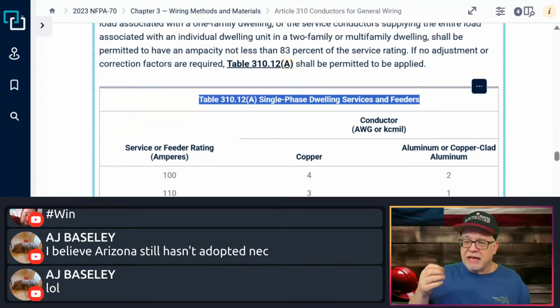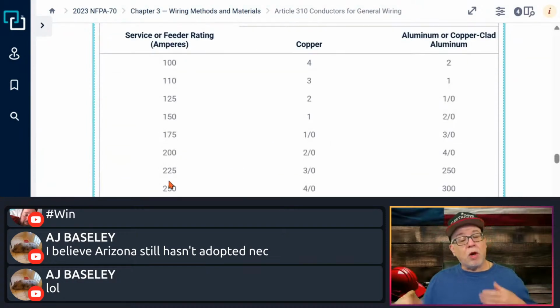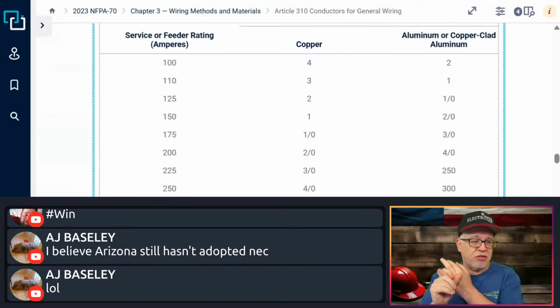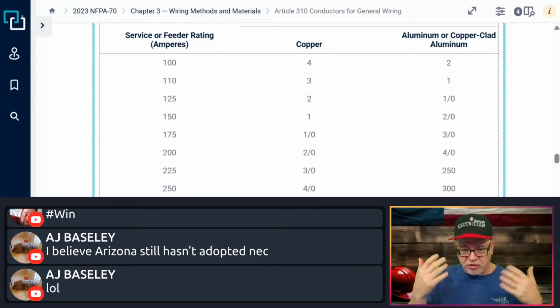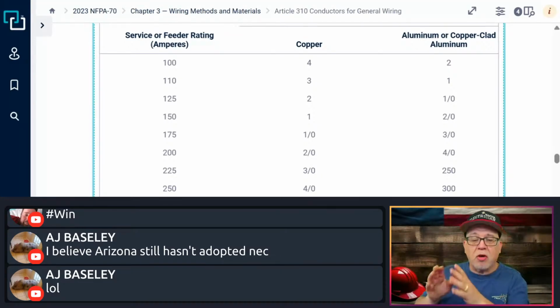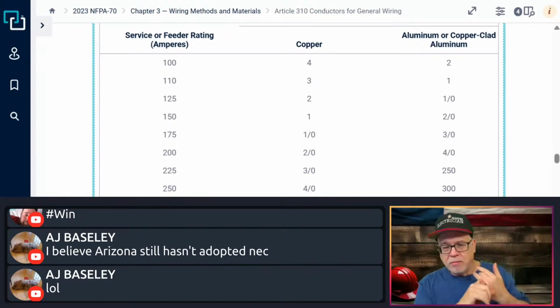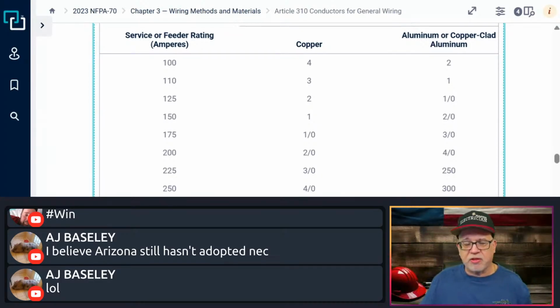And if they ask you a question and they're telling you the ampacities and it's falling between 100 and 400, they're telling you that it's single phase, 120/240, all these buzzwords, and then they ask you what the minimum conductor size has to be, then you know they're trying to get an answer based on 310.12, okay? And it's very much applicable. It's not an exception. Now, if you want to know how to size this stuff when there's an adjustment or correction, Brandon, I encourage you to go watch our video on derating demystified, because I go into all of the adjustment and corrections. And by the way, how you do this is no different than how you would do the adjustment and corrections for branch circuits or feeder applications. It follows the same principles.